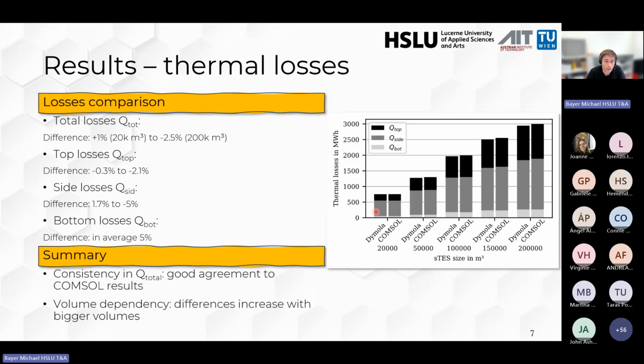As you can see in this chart, the side losses play a dominant role, especially as the size decreases. For large tanks, the side losses are roughly 50% of the total losses, and for smaller tanks, those increase up to 66% due to the higher surface to volume ratio. Bottom losses overall are the smallest contribution, ranging somewhere between 7 and 9% of the total losses.